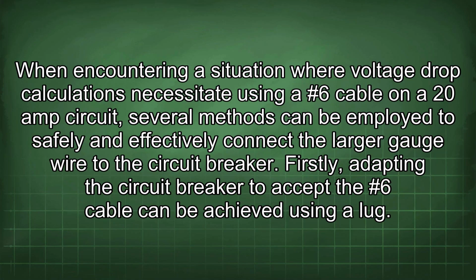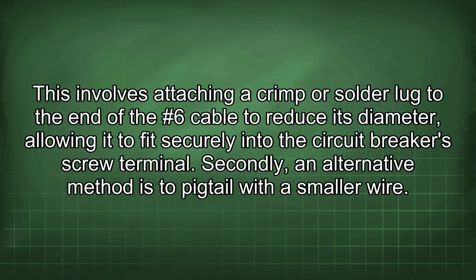When encountering a situation where voltage drop calculations necessitate using a #6 cable on a 20 amp circuit, several methods can be employed to safely and effectively connect the larger gauge wire to the circuit breaker. Firstly, adapting the circuit breaker to accept the #6 cable can be achieved using a lug. This involves attaching a crimp or solder lug to the end of the #6 cable to reduce its diameter, allowing it to fit securely into the circuit breaker screw terminal.